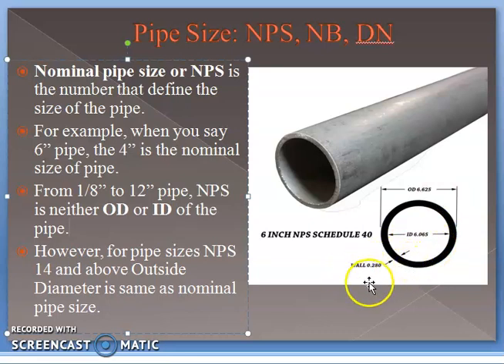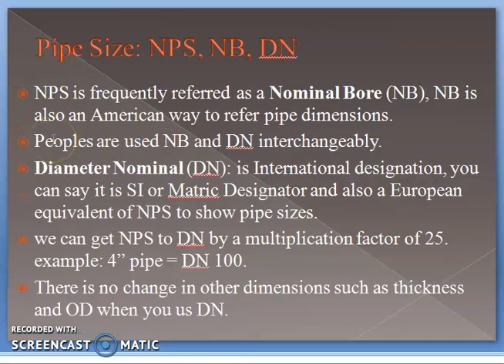The wall thickness is 0.280 inches. For the NPS system above 14 inches, the outside diameter is the same as the nominal pipe size. NPS is frequently referred to as Nominal Bore, which is also an American way to refer to pipe dimensions. NB and DN can be used interchangeably. DN — Diameter Nominal — is the international designation, equivalent to the SI or metric designator and the European equivalent of NPS.